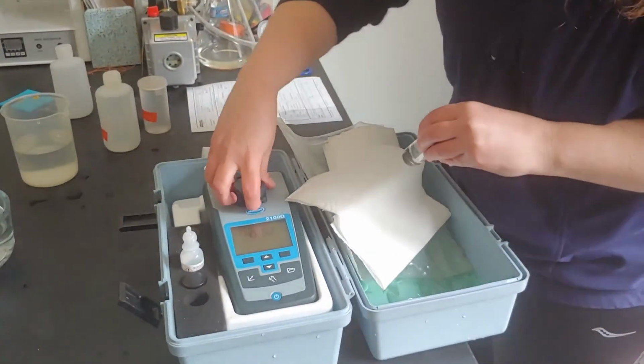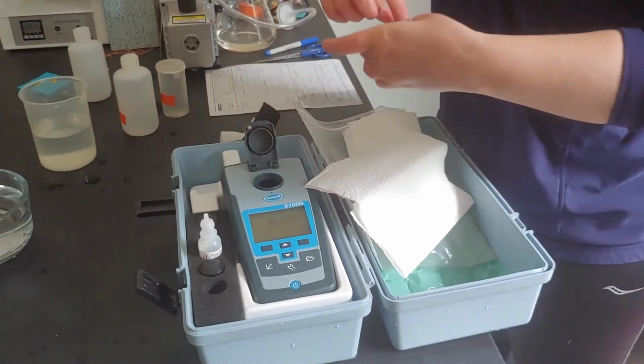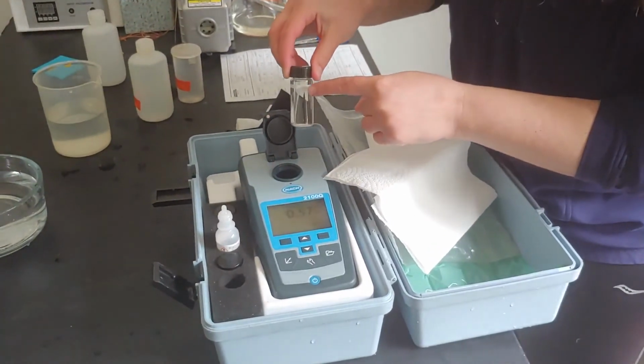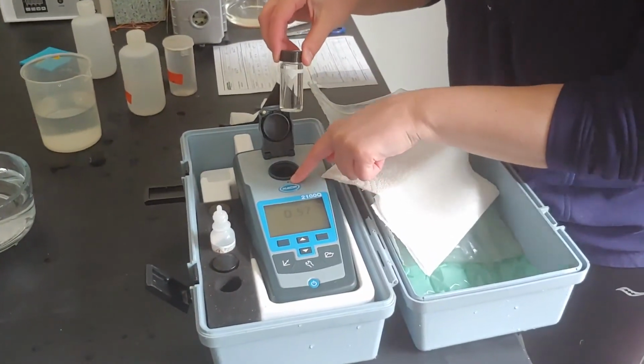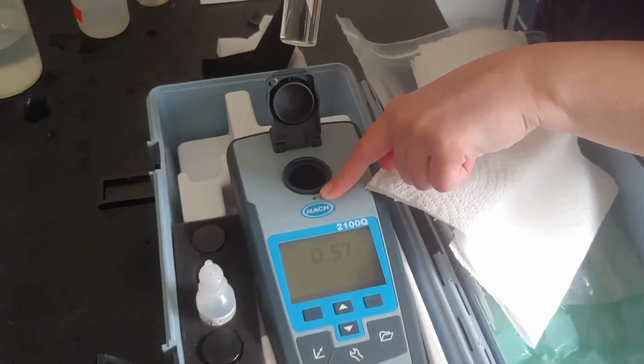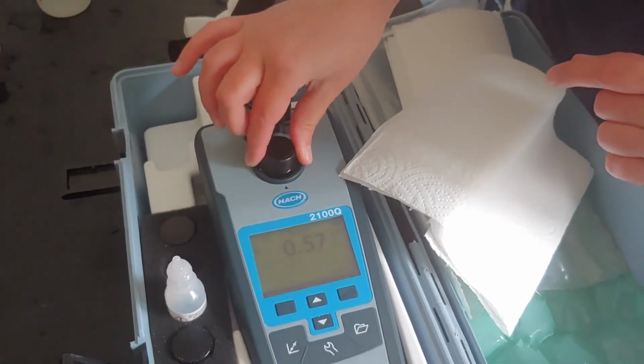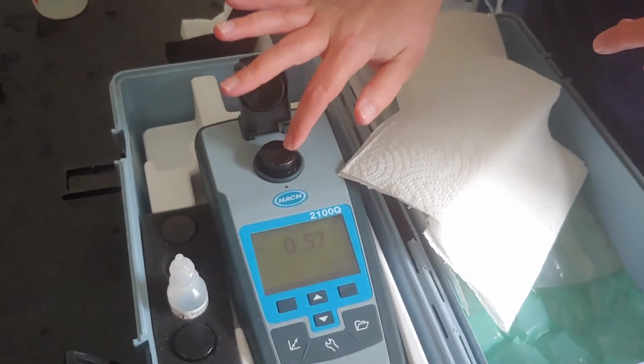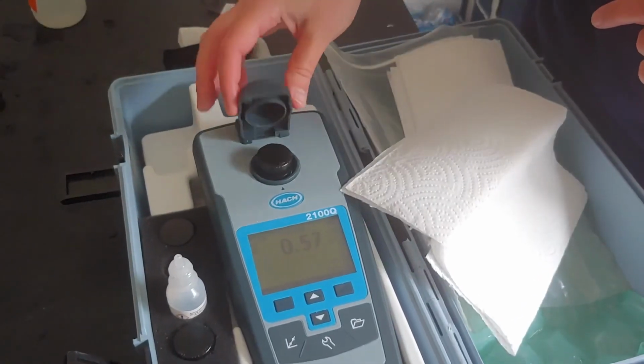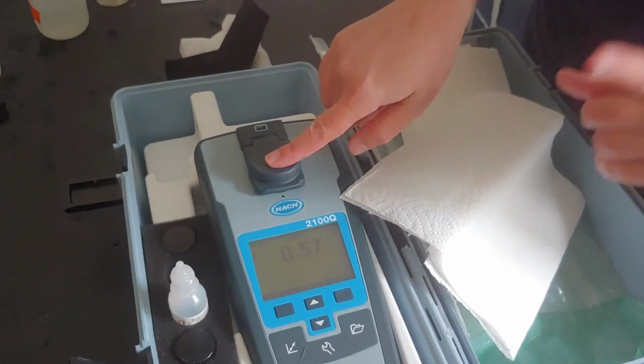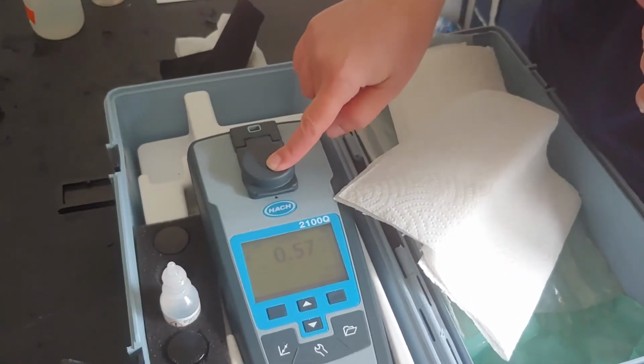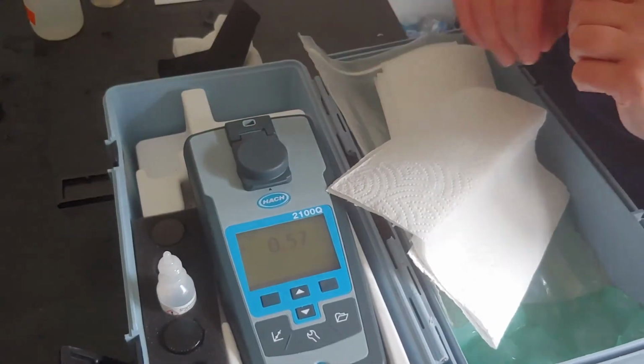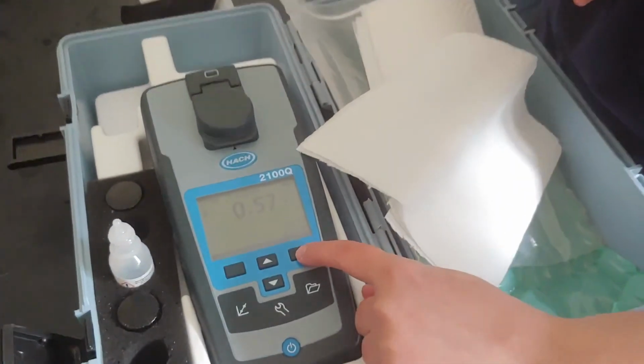From here, I'm going to open the top, and I want to align this white arrow here on the glass with the black arrow here on the Hach machine. You want to make sure that you push your cuvette all the way to the bottom until you can't push it in anymore. And then you want to push the cap down until you hear a click. Once you hear that click, now I'm going to hit the read button here.